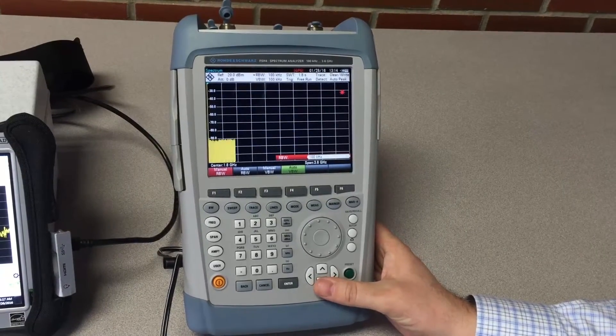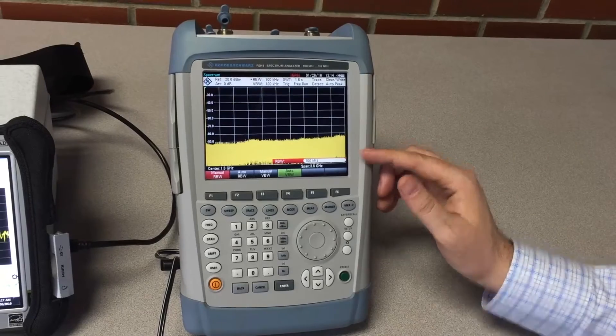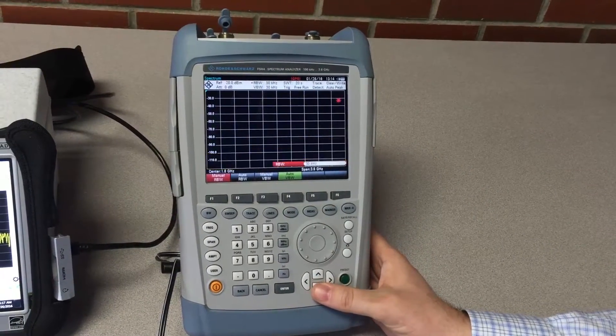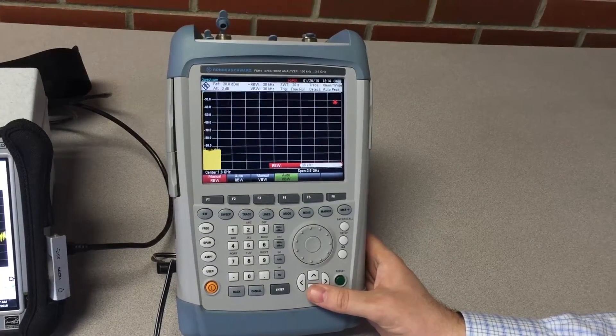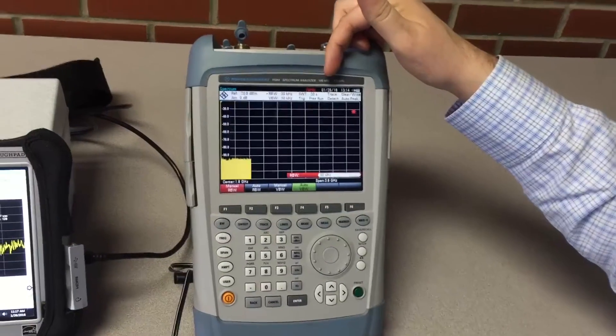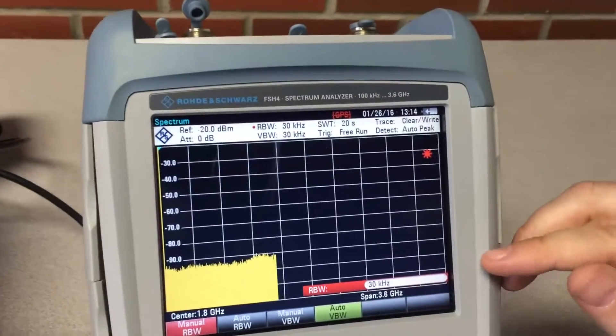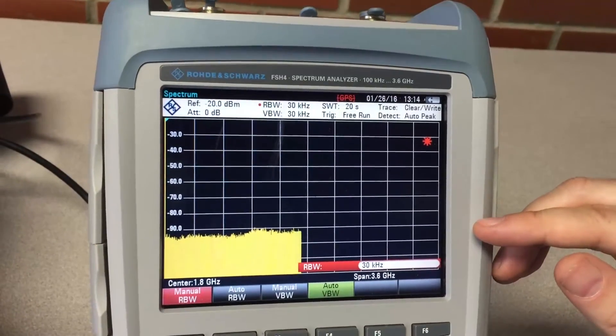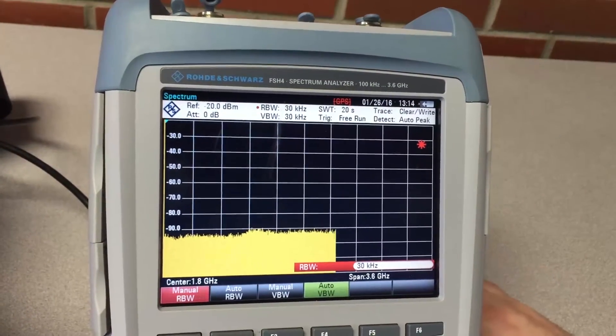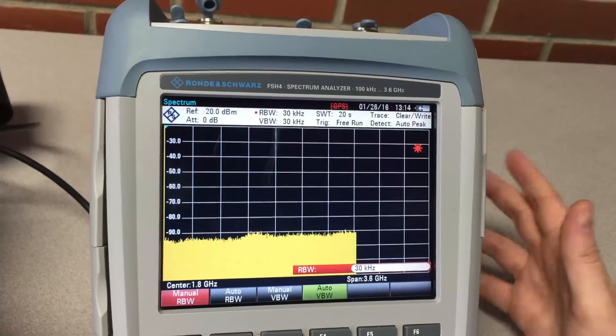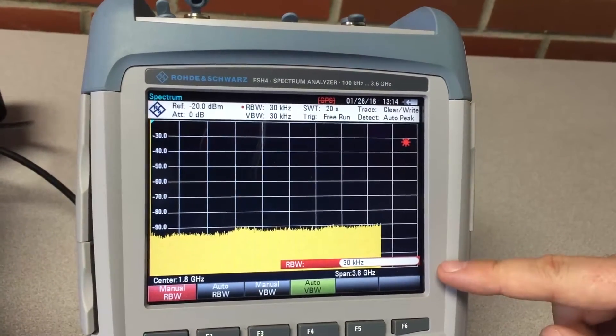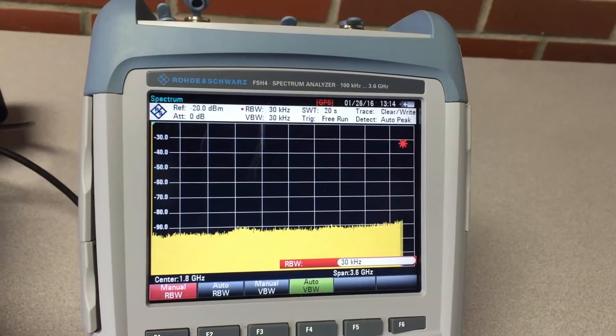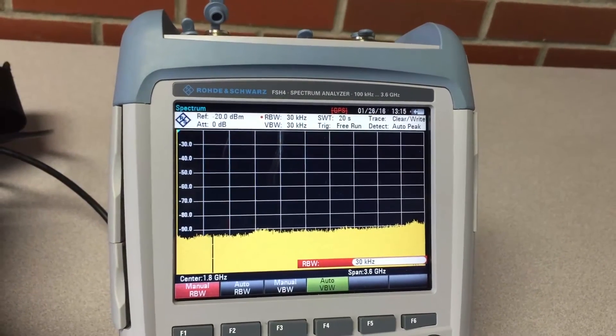As I continue to go lower, the noise floor is going down for the Rohde instrument. When I get to a 30 kilohertz RBW, the sweep time is now at 20 seconds, realizing around minus 90 dBm noise floor. I can play with the trace settings if I'd like. The point is to show the sweep time with that RBW is fairly long—20 seconds to do a full sweep of 3.6 gigahertz on the Rohde & Schwarz analyzer.